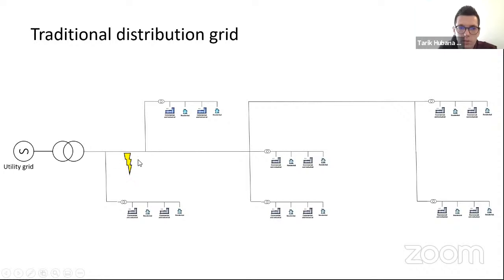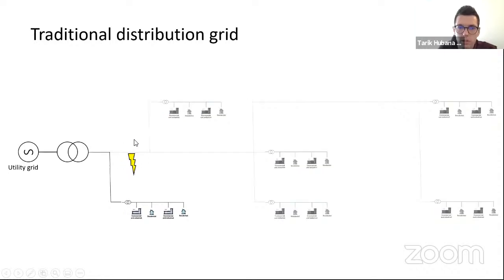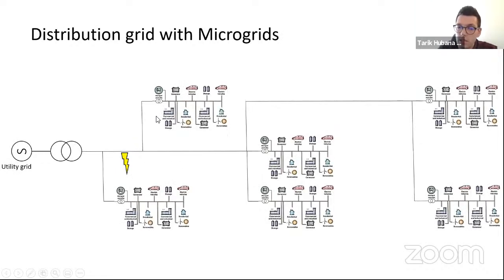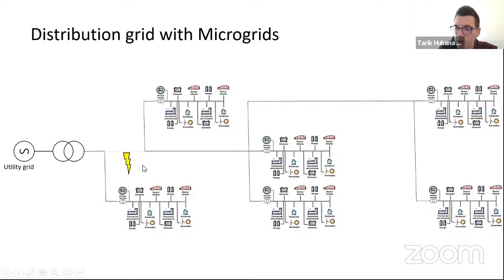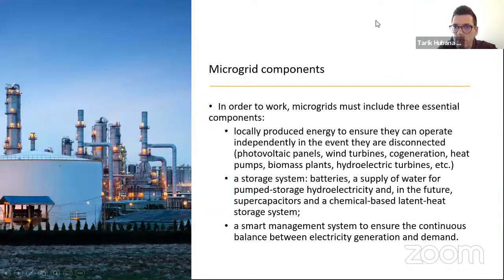So let's say a fault occurs at this part of the line. With the traditional distribution grid with radial feeders, all lower parts of the feeders would stay without electricity until this fault is cleared. But in the case of the microgrids, considering that all of these can go into island mode of operation, only this part, only the line or the cable with the fault, can be taken out of the system, and all consumers will have their energy supplied.